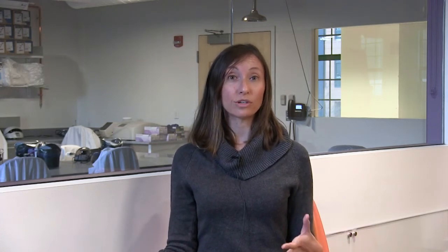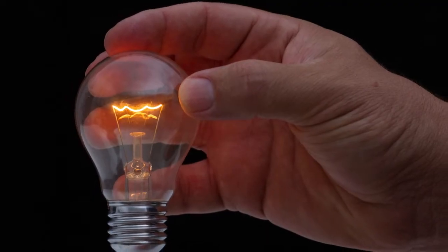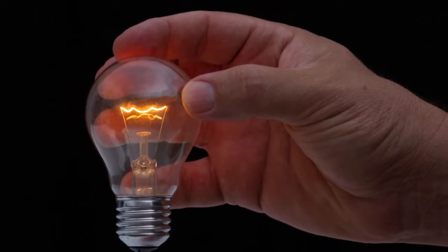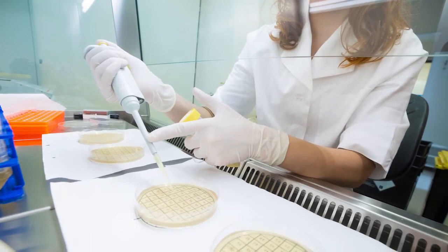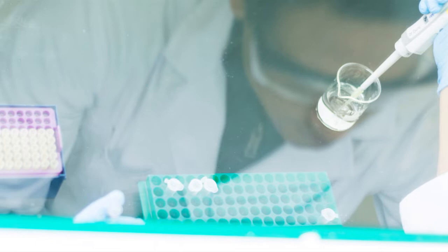As a former scientist, I never thought about energy consumption in the lab. It's really not visible to us, but it's everywhere — it's everything that gets plugged into the wall. When we think about energy consumption, we think about things like turning off equipment, or operating pieces of equipment more efficiently, like closing fume hood sashes, or adjusting the set point on freezers. The amount of energy you can save by closing your fume hood could potentially be more than any other thing that you do on a normal day as a researcher in the lab.